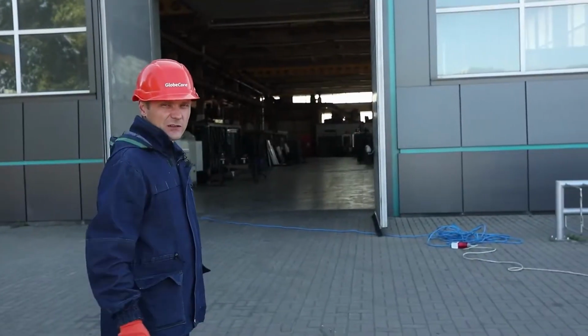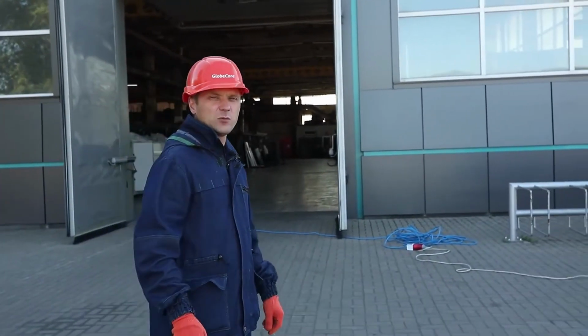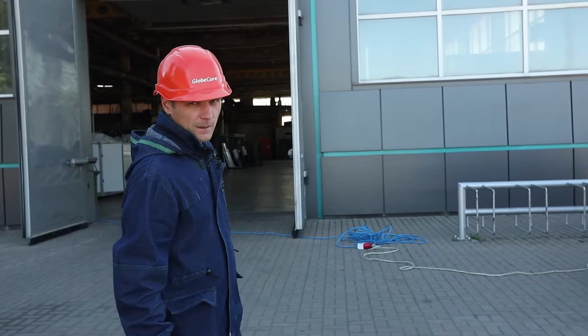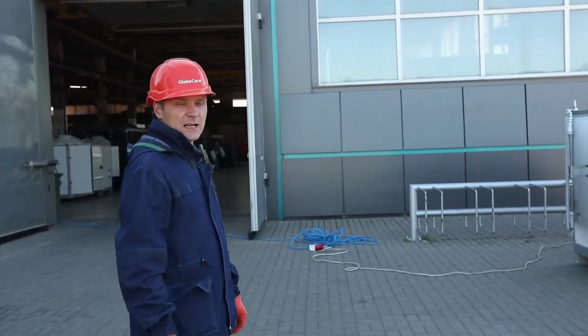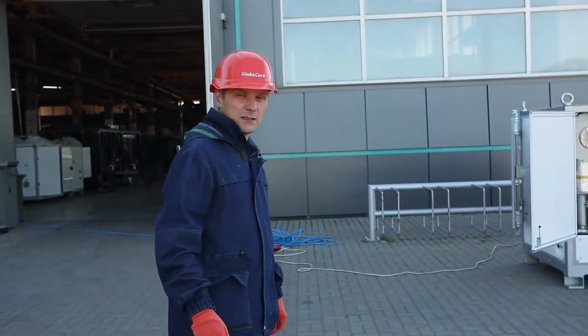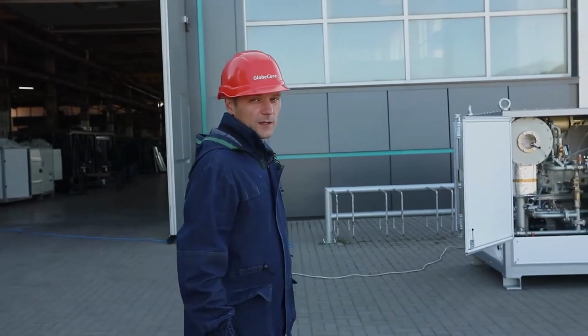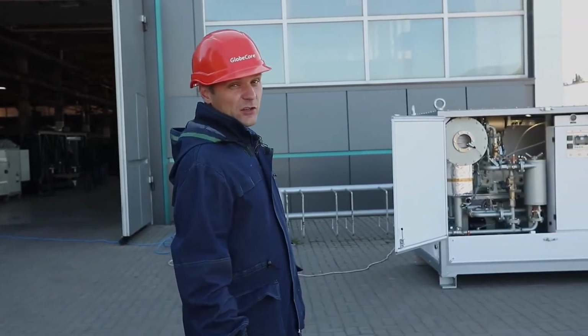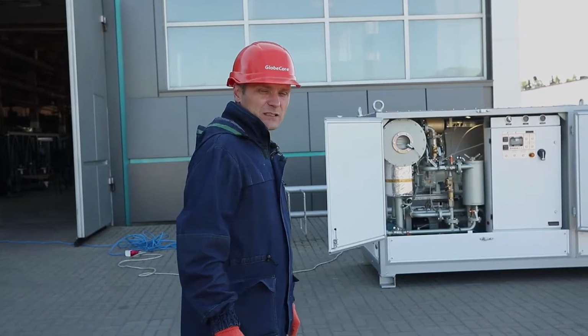Hermetic transformers with corrugated tanks require more powerful machines that ensure not only deep oil degassing, but also filling the transformer with oil under high vacuum. This kind of filling prevents premature oxidation of oil and decreases in dielectric strength of insulation.